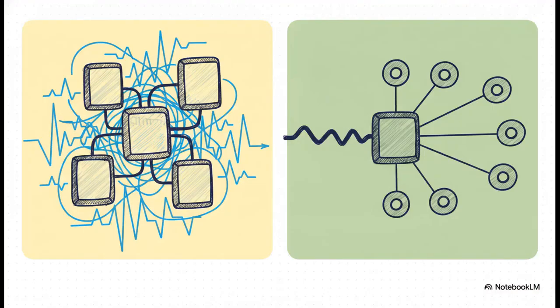When we compare these two main architectural choices, you're generally looking at either a single-drive or a multi-drive layout. In a single-drive setup, every individual motor has its own fully independent converter pulling directly from the switchboard. And because each one has its own independent rectifier drawing that pulsed current, harmonic filters are pretty much mandatory on every single unit. It's unit-by-unit filtration, which, as you can imagine, takes up a massive amount of physical space.